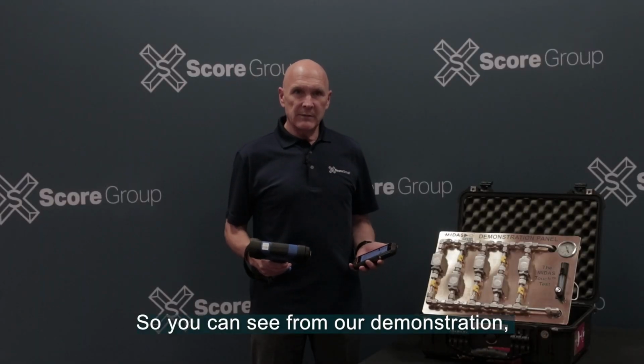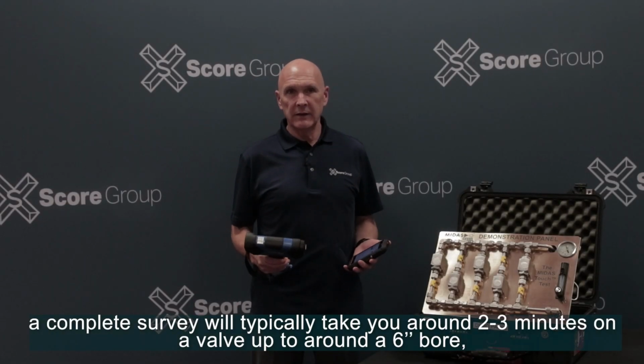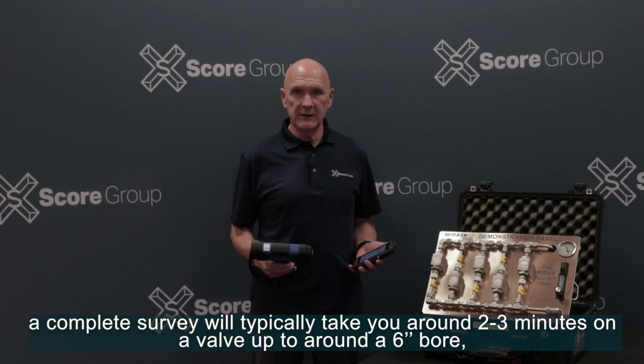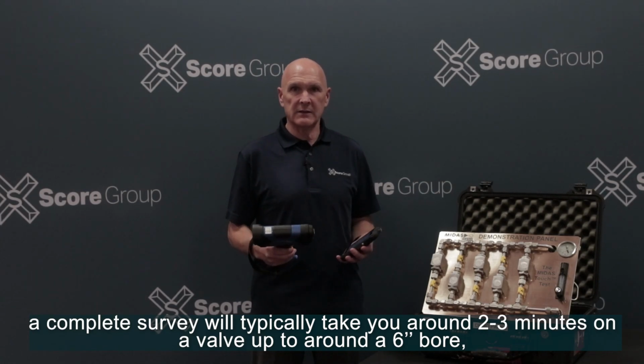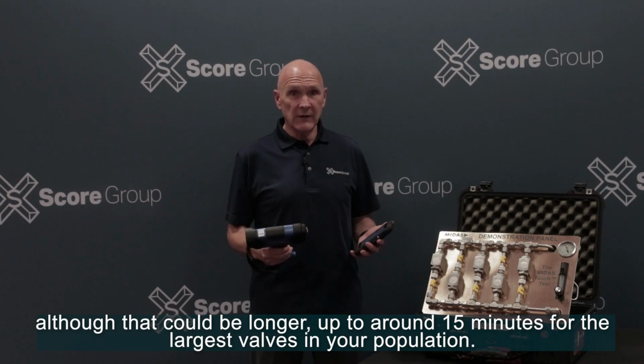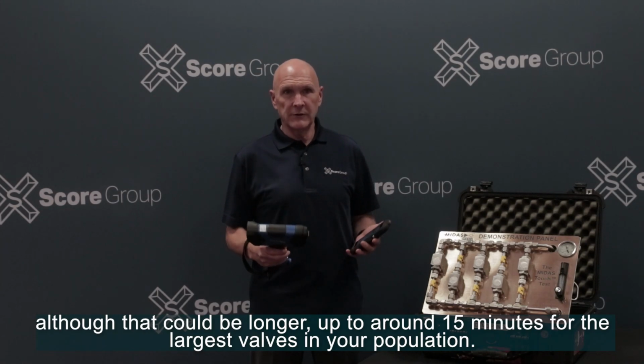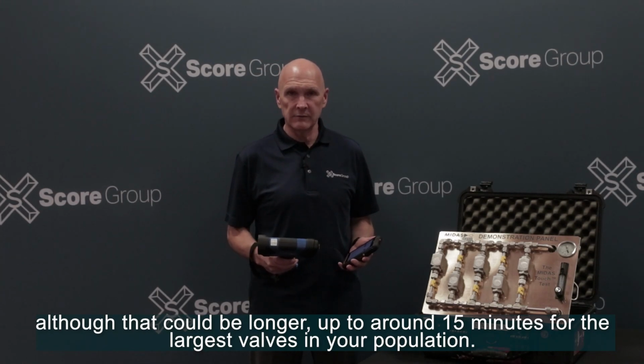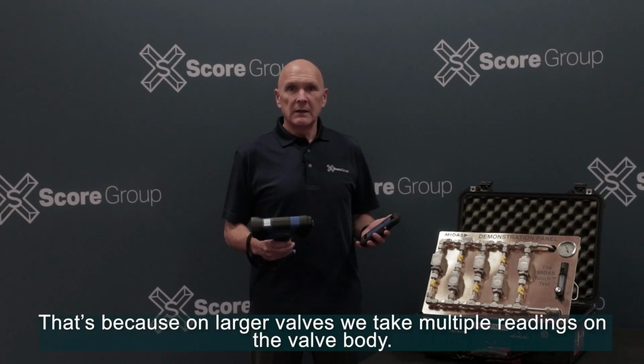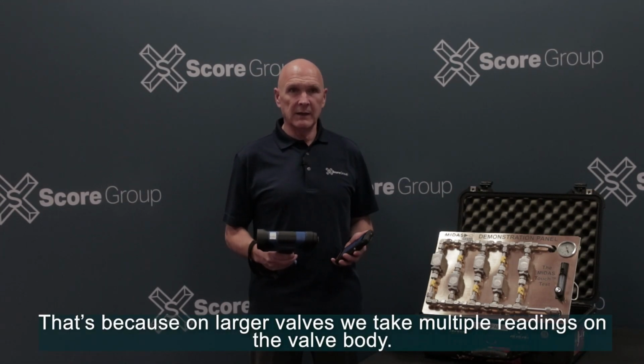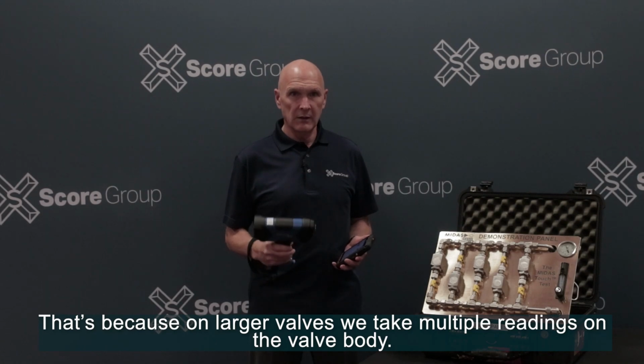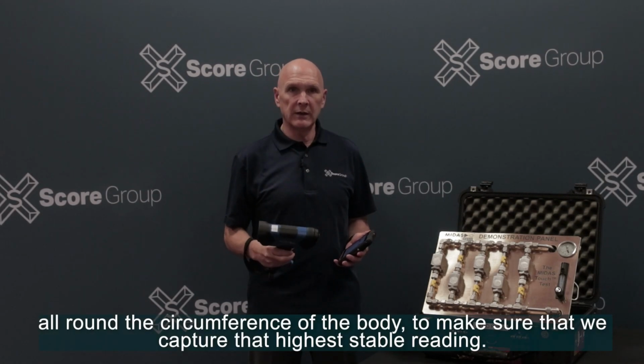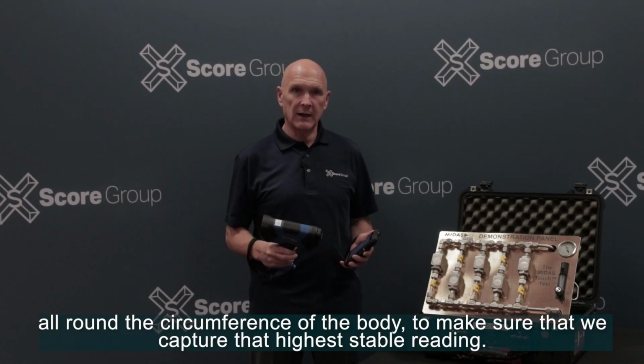So you can see from our demonstration, a complete survey will typically take around 2 to 3 minutes on a valve up to around 6-inch bore. Although that could be longer, up to around 15 minutes for the largest valves in your population. That's because on larger valves, we take multiple readings on the valve body, all around the circumference of the body, to make sure that we capture that highest stable reading.